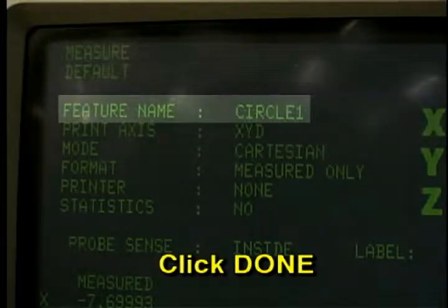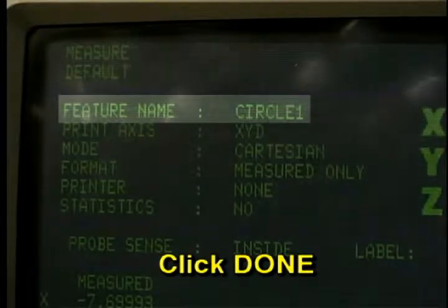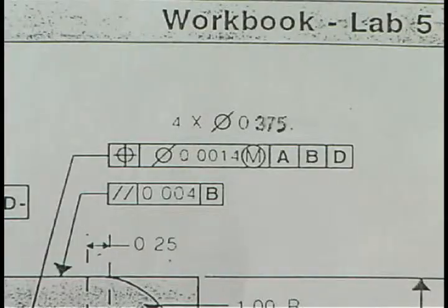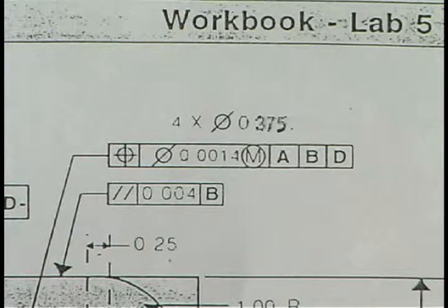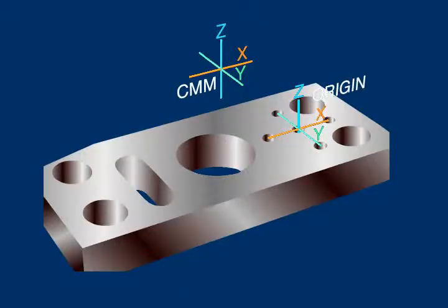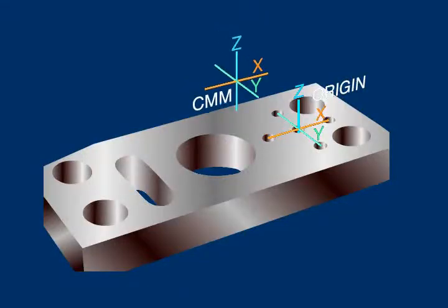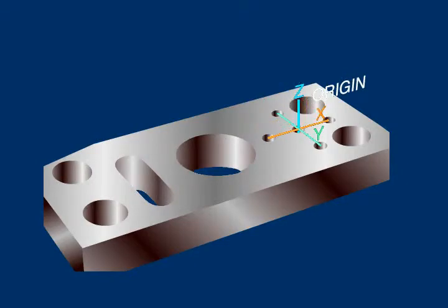Click Done to complete the process and return to the main menu screen. To complete the alignment, the computer must be told to use these reference surfaces as the axes for this next set of measurements. This will align the zero point on the CMM with the zero point on the workpiece as specified by the print.